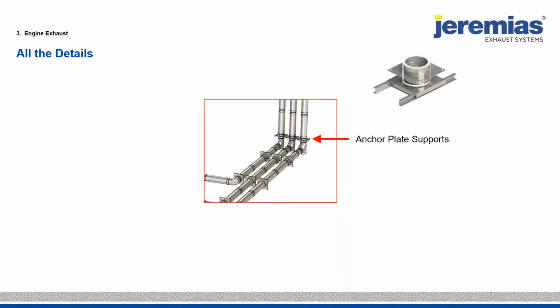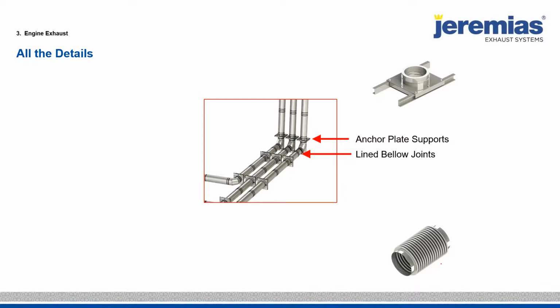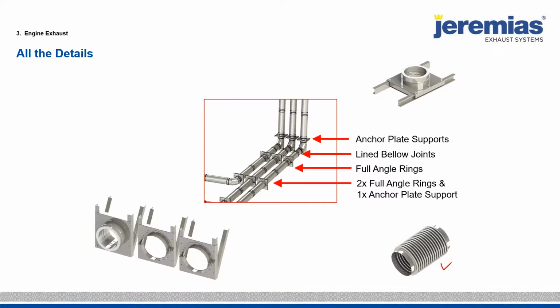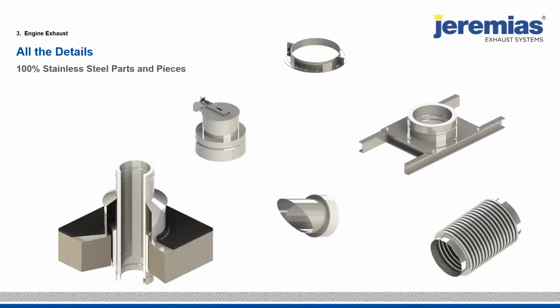Now, we supply all the anchor plate support, so you have a lot of expansion. For example, 10 feet of stainless steel ductwork is going to expand 1 inch at 1,000 degrees and then contract again. So what we do is we anchor the plates at every change of direction. We supply the bellows whenever expansion exceeds 3/8 of an inch. We supply all the struts and guides to make sure that the pipe stays intact. All the drains, we always put drain sections on engine exhaust systems. You have a ton of condensate at startup. Some of the accessories I want to point out, the insulated roof thimbles, no ventilation needed. The bellow joints are actually lined.